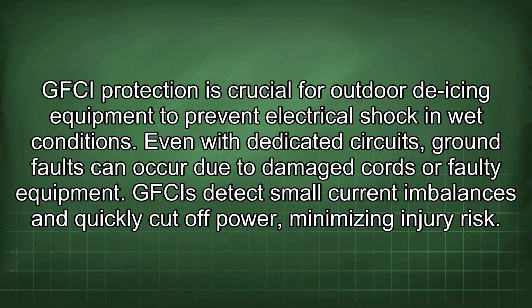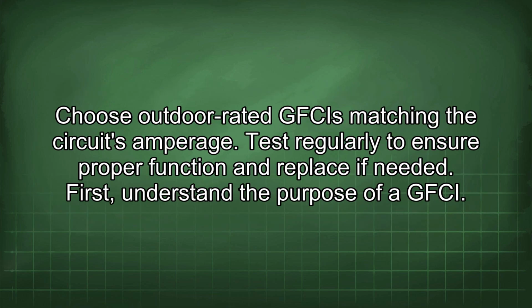Even with dedicated circuits, ground faults can occur due to damaged cords or faulty equipment. GFCIs detect small current imbalances and quickly cut off power, minimizing injury risk. Choose outdoor-rated GFCIs matching the circuit's amperage. Test regularly to ensure proper function and replace if needed.